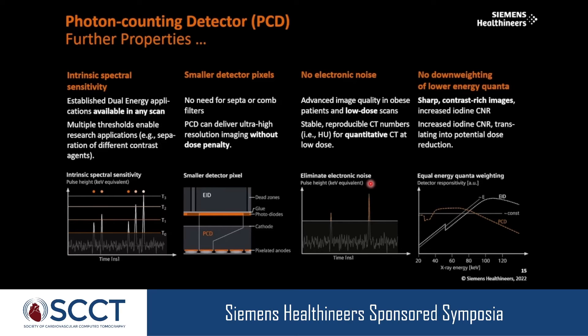Summarizing the properties and benefits of a photon counting CT detector: intrinsic spectral sensitivity allowing derivation of all spectral data; always available high resolution capability; no electronic noise since only pulses above a threshold are counted; and no down-weighting of low energy quanta — they equally contribute to the signal, unlike traditional energy integrating detectors where high energy quanta contribute disproportionately more.